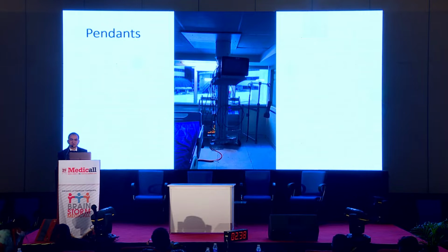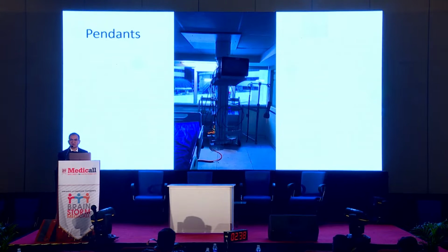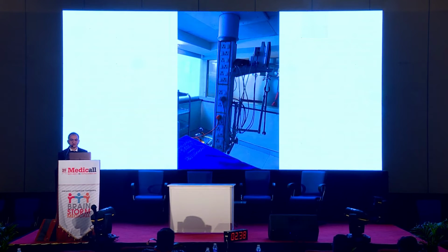This is the vertical ceiling suspended pendant, or the ceiling suspended bed panel, through which we get the electrical points, gas points and network points. There are two clear sections, one supplying raw power. If you want to put a portable X-ray machine, you connect it to raw power, or if you want a syringe pump, infusion pump or monitors, you connect it to the UPS points. So this is very important.